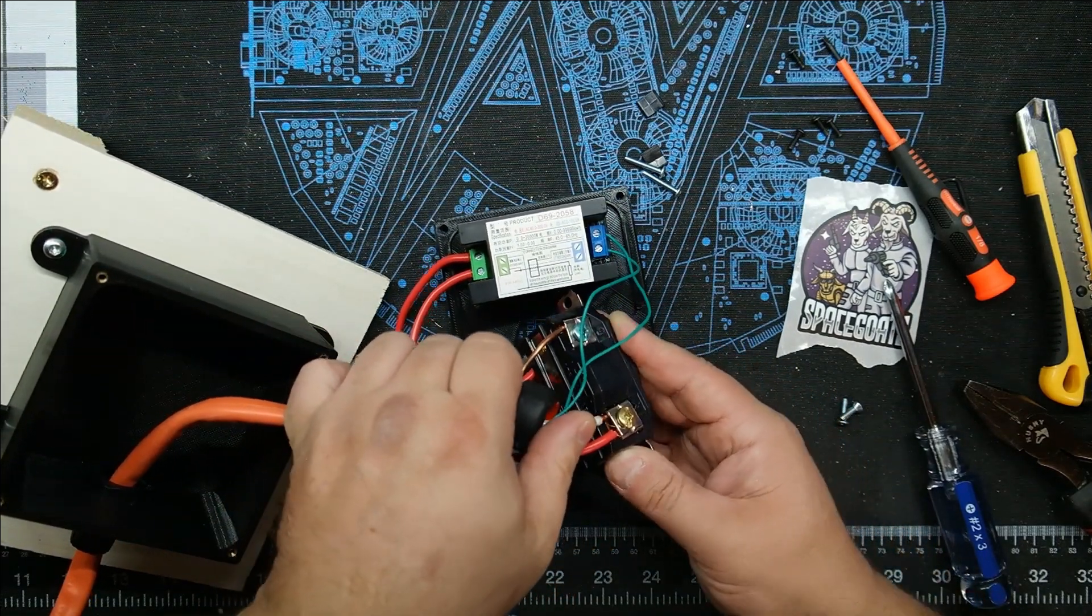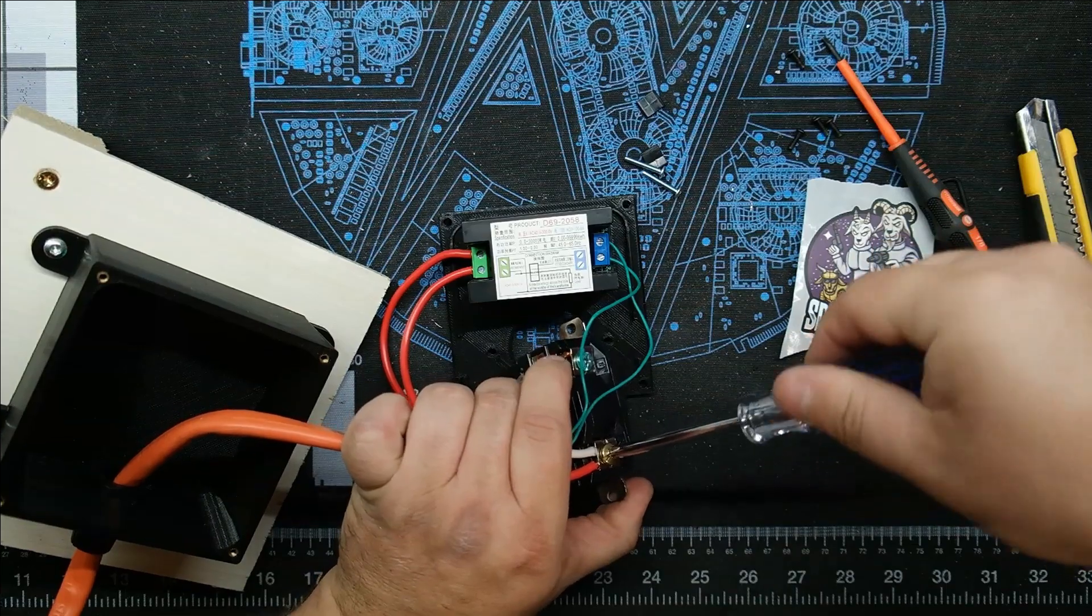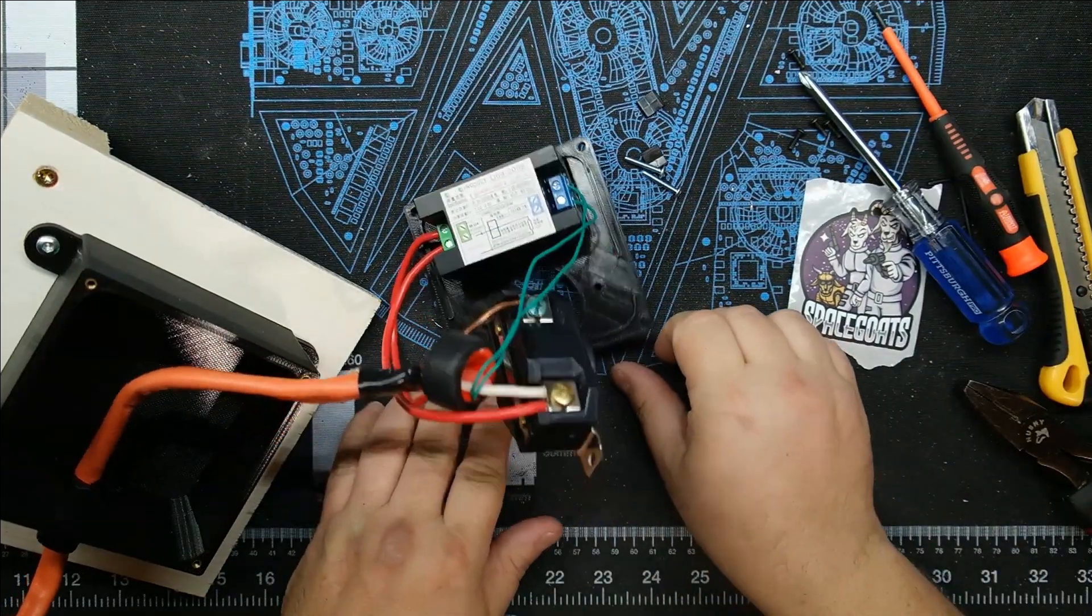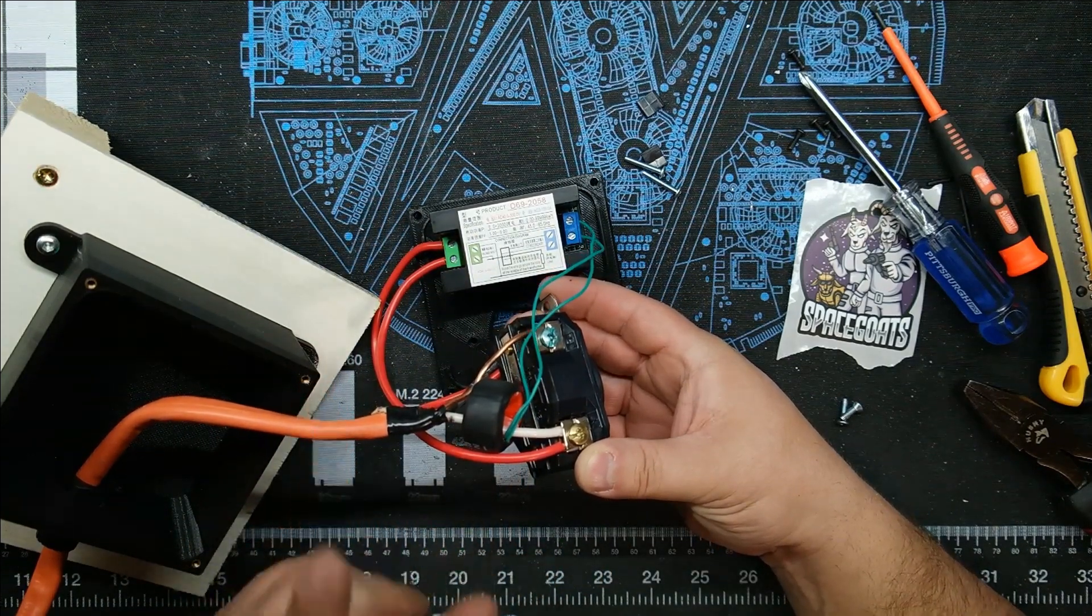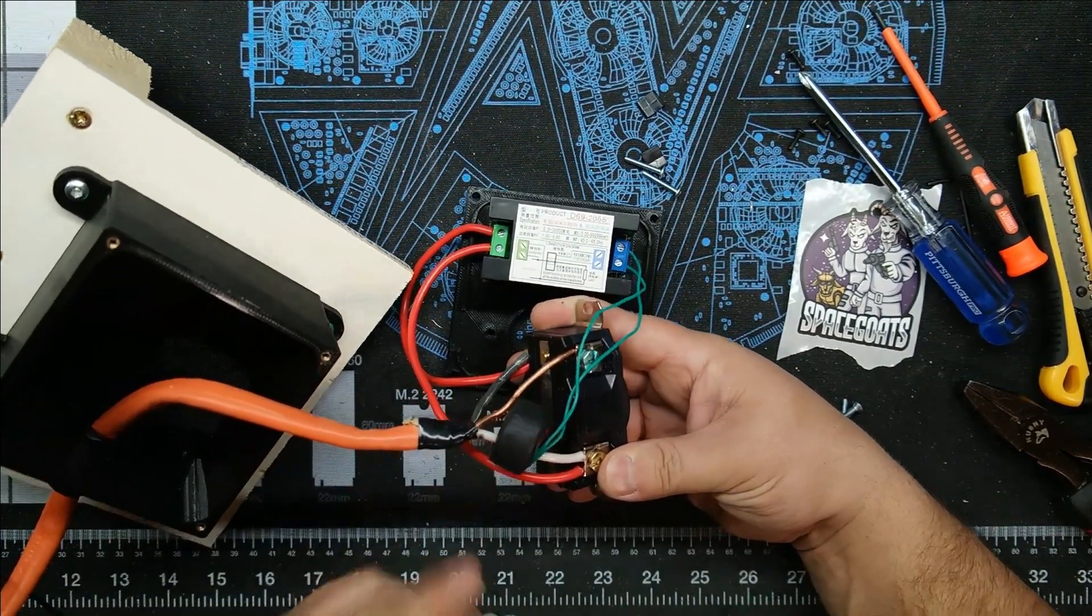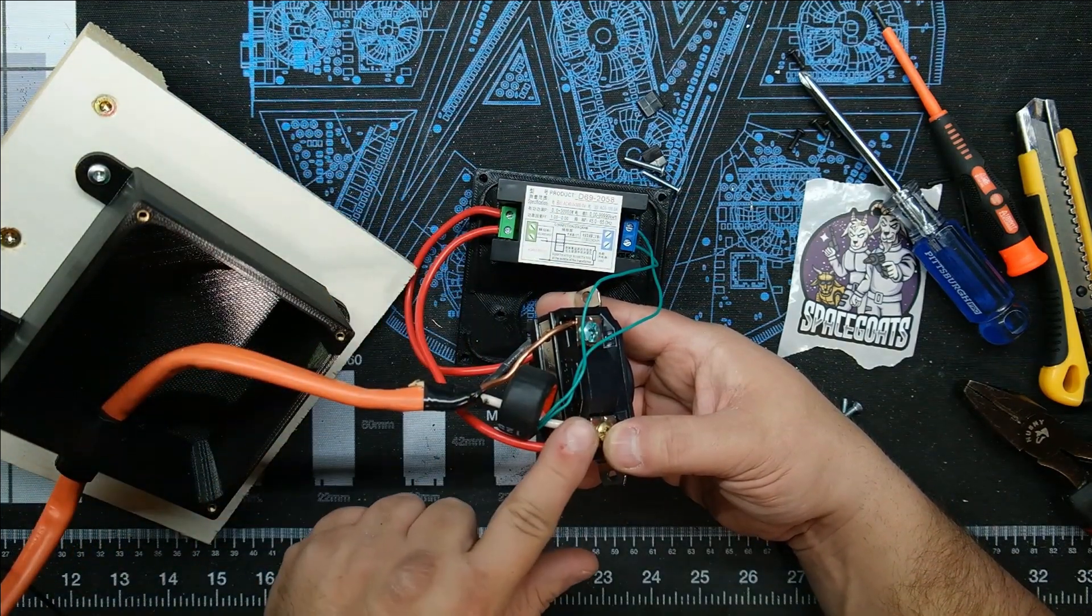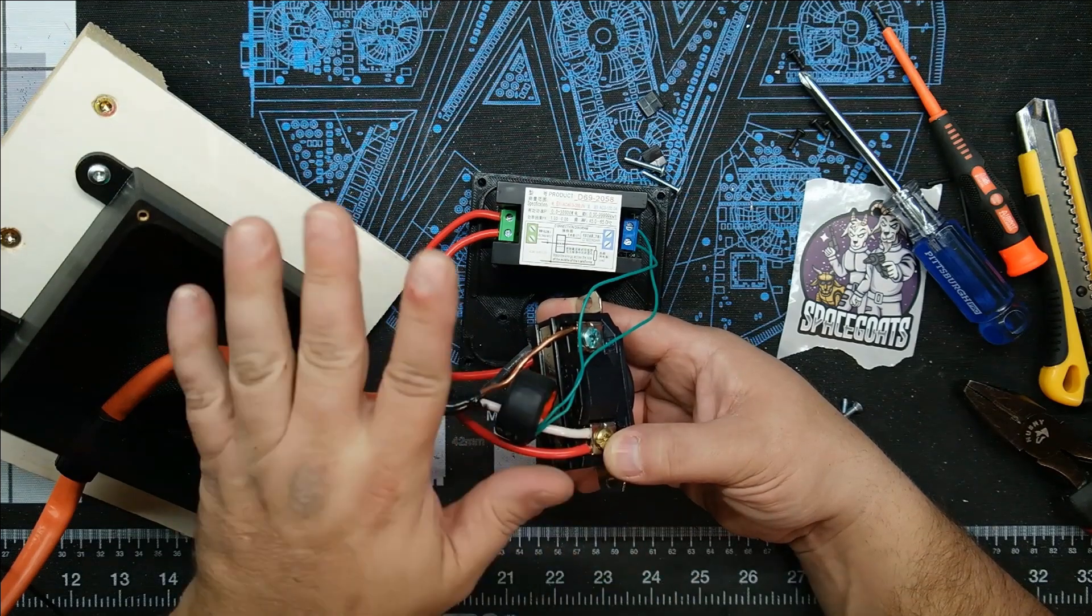Let's put this back together the right way. Let's do the explanation again: ground is green right here right from your supply line. I have two hots - one is white, one is gray. Right down here there's my other hot. The two power lines from the display come on over and attach to each hot. The coil goes around one of the hot wires - doesn't matter which one, just one of the hot wires. That's how it reads.